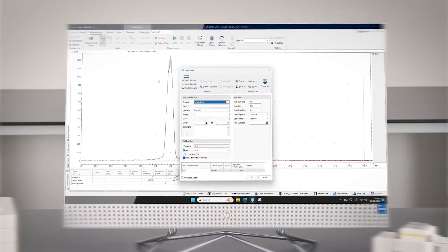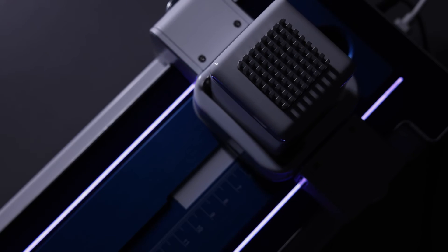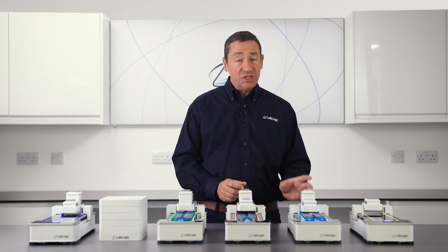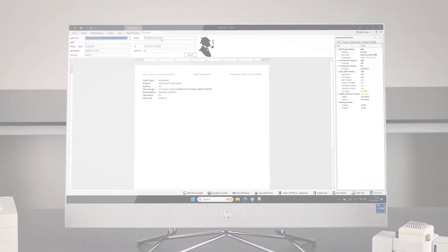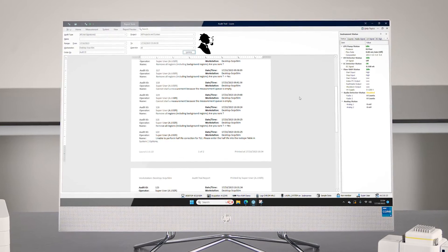Speed, maximum count rates, and scanning time can all be easily configured in the software method. It is important to note that no settings can be physically changed on the instrument itself. This can only be done using Laura software, which features a full audit trail.